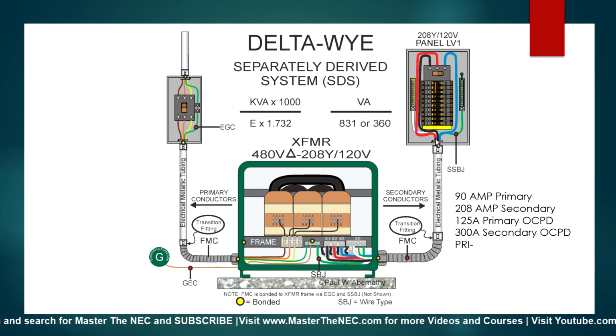So when we go to 310.15(B)(16), we'll see that these need to be 350 kcmil, which is good for 310 amps, because the size below was only good for, I don't remember exactly, like 285 or something like that. It wasn't good for 300 amps. Since this was 300 amps, it had to terminate in a 300, and you can't use the next size up rule because it says you can't in 240.21(C). All right, so that's what they are.